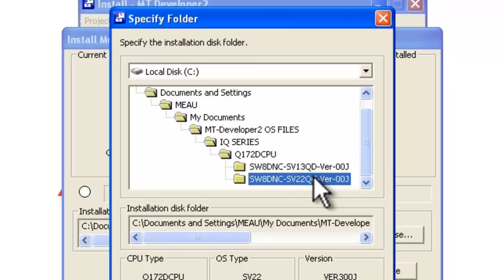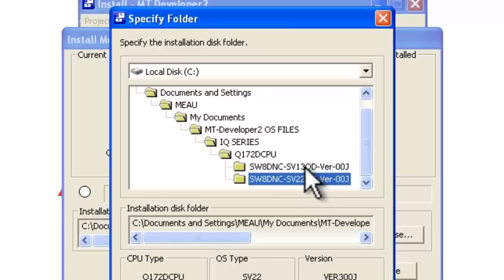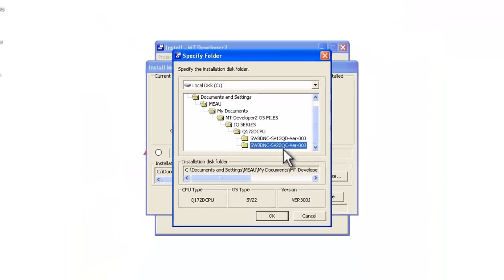SV22 is referred to as virtual mode and includes electronic line shaft programming, electronic clutching, electronic camming, and more advanced positioning operations. In 9 out of 10 cases, you'll want to use SV22, since this also includes the SV13 functionalities.